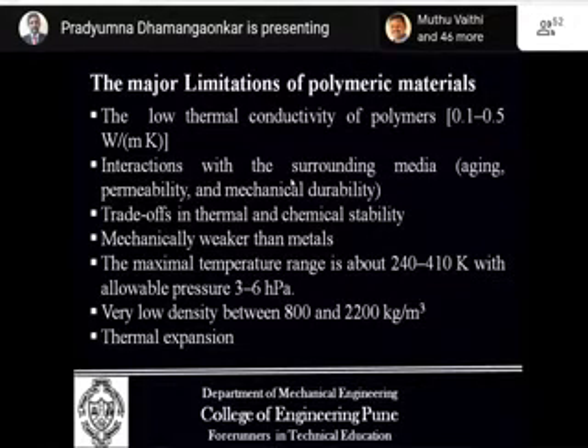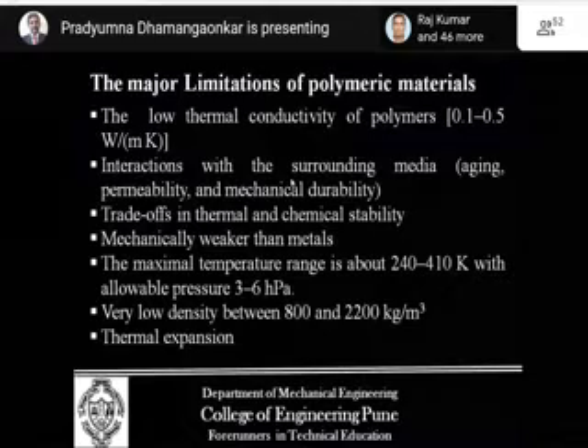And the greater problem with the polymer is thermal expansion. The coefficient of thermal expansion of polymer and metal are really not comparable. So this polymer material will have higher thermal expansion as compared to the metallic heat exchangers, and hence these are more prone to deform if they are not properly supported, not properly fixed, not properly strengthened.